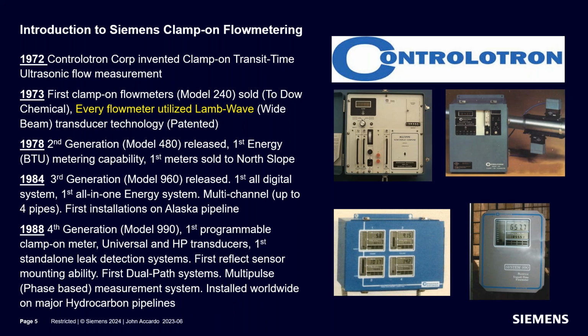When you have a programmable meter, now you kind of dig yourself a hole, because now you can take a meter and go to any pipe you want and just program the configuration of that pipe, what size it is, what kind of material it's made from, what the wall thickness is. But then you need the right transducer for that pipe. So we were faced with the dilemma of having a very easy to program flow meter and the need for a truckload of transducers. So we developed and released what we called universal transducers at that point, which were technically shear wave transducers.